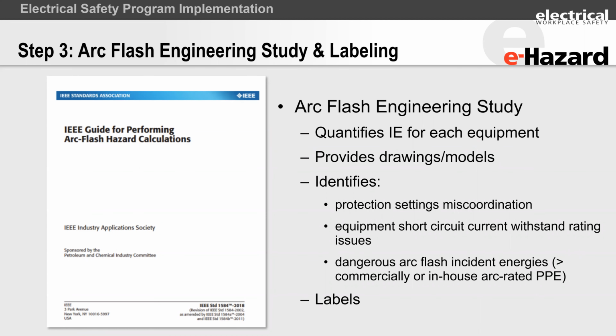Basically, it's an engineering study that models all the 3-phase electrical equipment that you've got in your plant. In addition to identifying your incident energy, which it does via labels, it has the benefit of identifying protection settings. Sometimes you would notice that you have a small failure at some random location in your plant, and it trips up the main circuit breaker, and then you lose power to the entire plant.